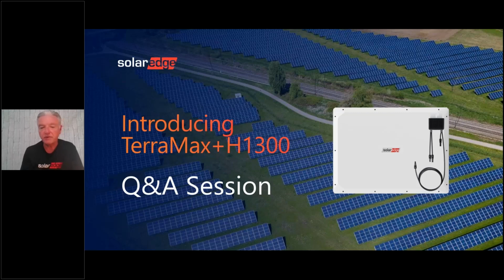We can identify ground faults and exactly where in a string things are going wrong. So our monitoring system gives us a very comprehensive, very visible view into the system and the health of the system. For your regular schedule of maintenance, either every 6 months or every year, you would check your torque values and do your visual inspections, making sure there are no fans that are clogged up. If the fans have failed and they're not working, that too alerts to the monitoring portal. All of those things will help you to identify problems and know the health of your system and whether you really have to go out to the site and do any mitigation work. So, your regular scheduled maintenance, and then using our monitoring portal to make sure the health of the system is good.